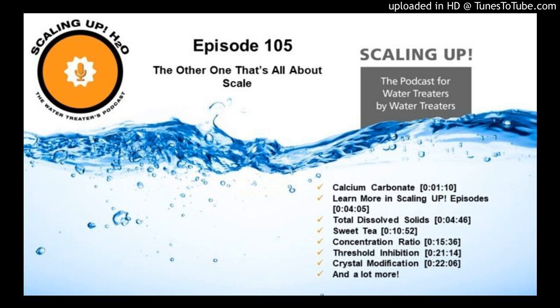So whatever we are doing to take away one of the 5 components, and we're probably not going to do anything with heat, and with conductivity, we talked about what we can do with that. That's how we're managing our bleed. So the only real other ones that we can look at are alkalinity, pH, and hardness. So if we do something with that, perhaps we can extend the concentration ratio.